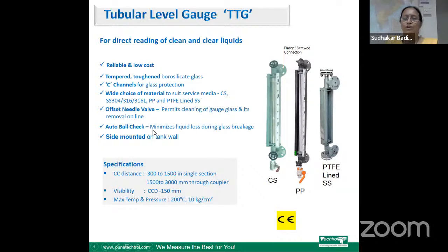Then offset needle valves with auto ball check facility are provided along with these level gauges. These gauges are mounted on the side of the tank wall, and you can see the liquid level through the gauge glass. These gauges are available for the range up to 1500 mm CC distance in a single section, and beyond that, up to 3000 mm, you will get it in coupler connections. The visibility of this gauge will be CC distance minus 150 mm, and these gauges are suitable for a maximum temperature of 200 degrees Celsius and pressure of 10 kg per centimeter square.